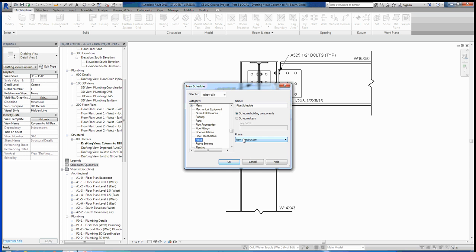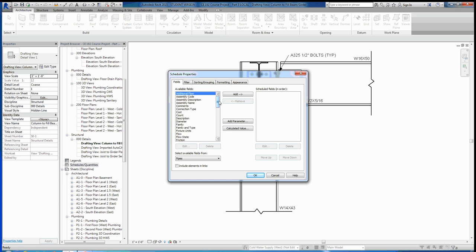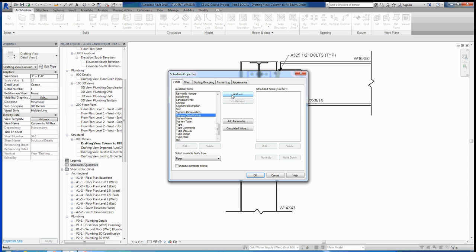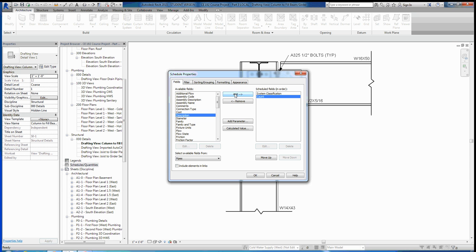Now you'll see here in the field you can choose which fields you want to include in this schedule. In this schedule, we want to include four things. The first thing I want to include is the system classification, so we'll scroll down to system classification and add that into the fields that we're going to be scheduling. Then we can scroll up. I also want to include the count, so how many of these there are. I want to include the size, so we'll scroll down to size and add that. And then I also want to include the length and add that as well.